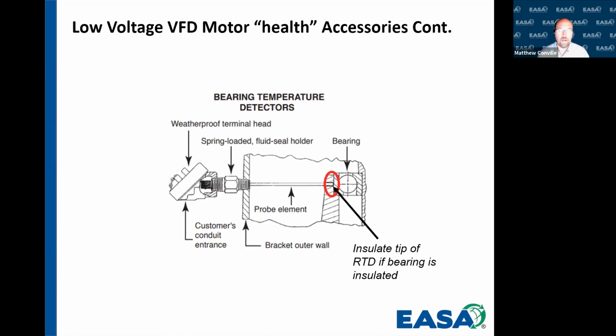The one thing we have to be careful about now that we're using a variable frequency drive, or even in some instances without a variable frequency drive, is that as soon as we put this RTD in contact with the bearing, you have metal on metal contact. If this bearing or this housing is considered to be isolated, we've now created a ground path from the probe, the detector shaft that's usually made out of stainless steel, back to the frame or the end bracket. So now we're going to allow current to flow through the bearing, and we can create fluting as a result of that. So when we buy RTDs that we're going to sit onto a bearing, and we're going to use them in a variable frequency drive application or one where we have isolated bearings, we want to get an insulated tip for the RTD.